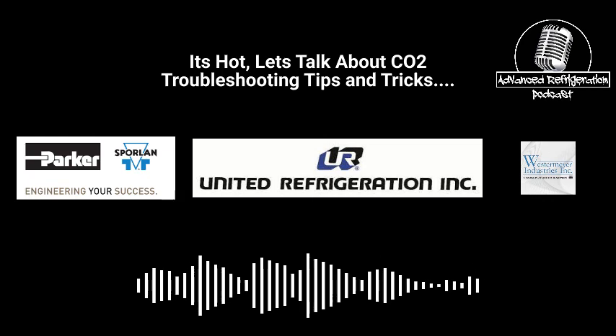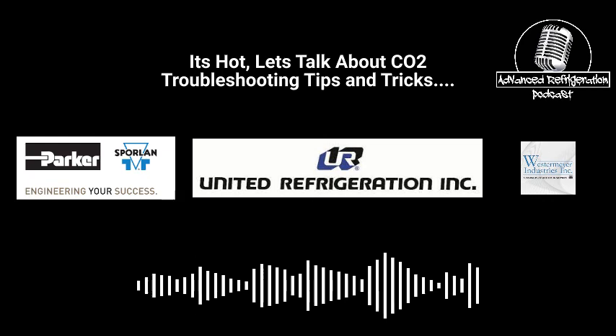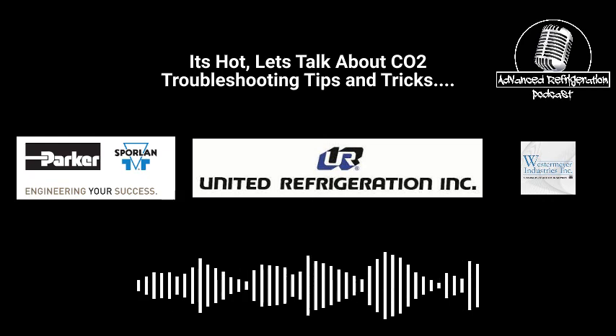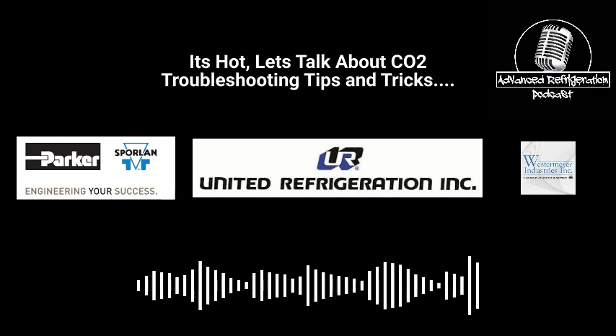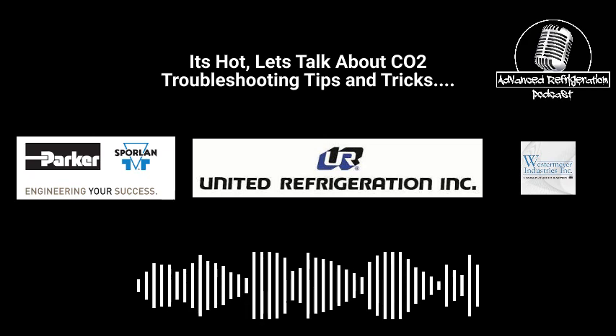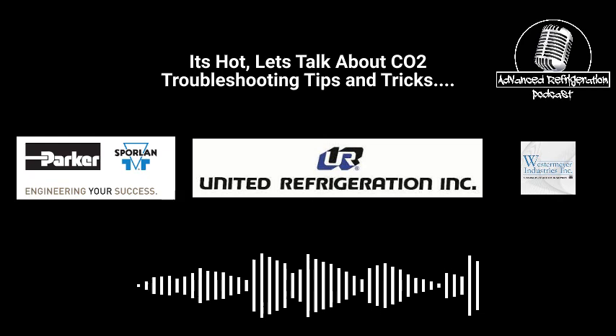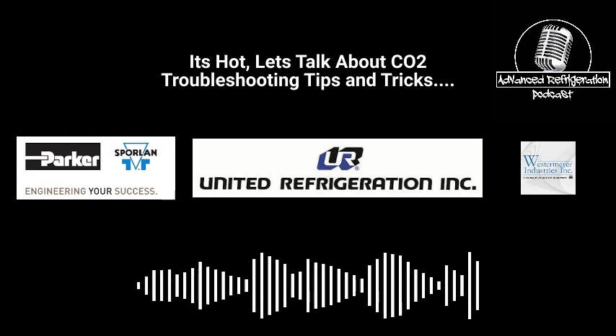We had to keep raising, I think, N82 or something like that, to raise the maximum operating gas cooler pressure, just temporarily, to get the thing to roll. So what was the receiver pressure doing? It was high at that point. It was about 572. That's why it was shutting down. There's that P band for the max receiver pressure. I don't remember exactly what it is, but it's in that band where it starts shutting down the HPV to protect the receiver.